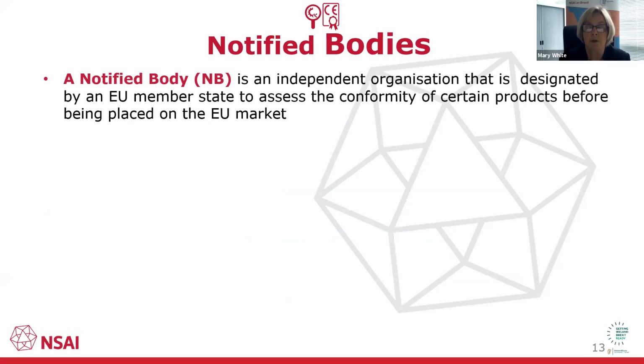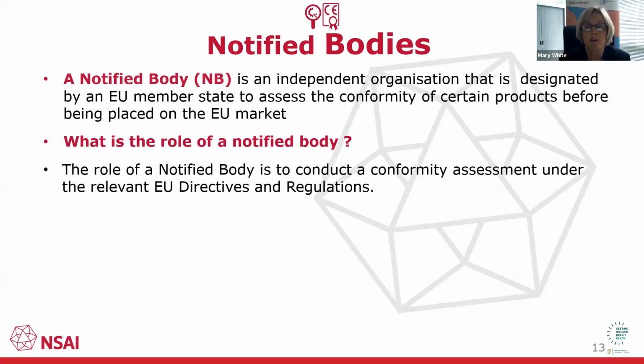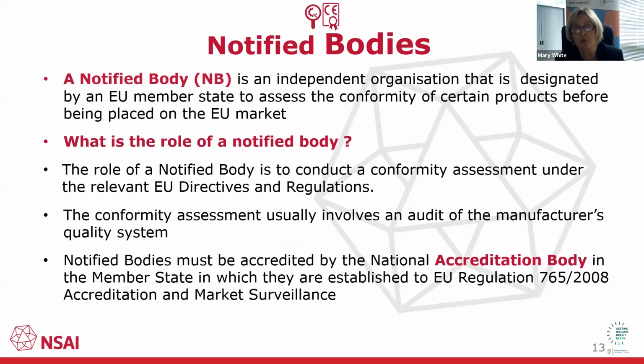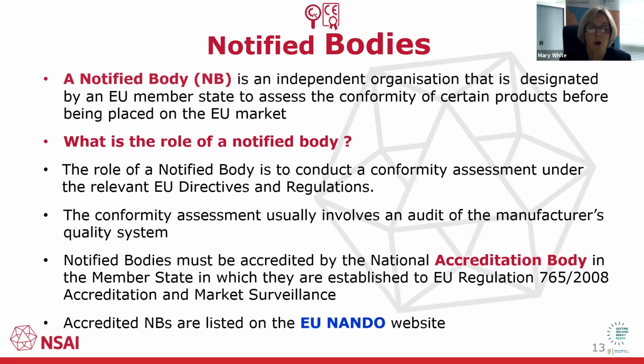I'm now going to talk to you about notified bodies. A notified body, which you require for third-party certification, is an independent organisation that is designated by an EU member state to assess the conformity of certain products before being placed on the market. And what is their role? The role is to conduct a conformity assessment under the relevant EU directive and regulation. The conformity assessment usually involves an audit of the manufacturer's quality systems. Notified bodies must be accredited by the national accreditation body in the member state in which they are established, under EU Regulation 765 of 2008, which covers accreditation and market surveillance. A list of all these notified bodies is on the EU NANDO website, and there are 1,500 notified bodies currently.